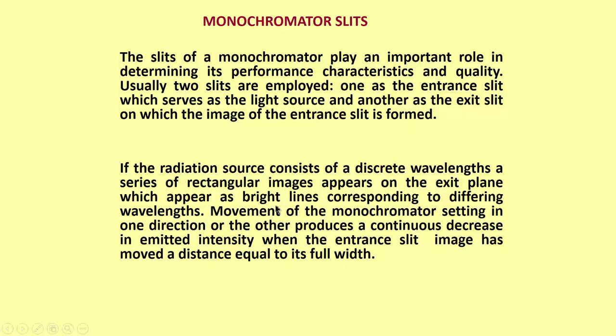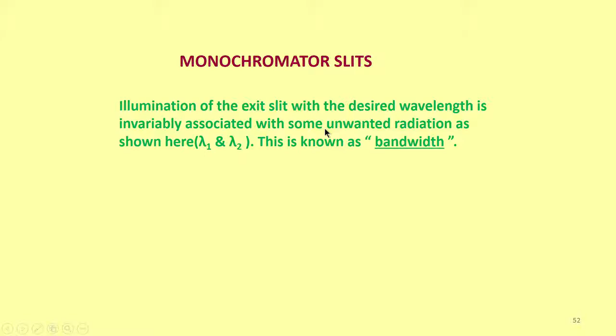So, if the radiation source consists of discrete wavelengths, a series of rectangular images occur on the exit plane, which appear as bright lines corresponding to different wavelengths. Movement of the monochromator setting in one direction or the other produces a continuous decrease in the emitted intensity when the entrance slit image has moved a distance equal to its full width. So, this is what happens actually in slit management.